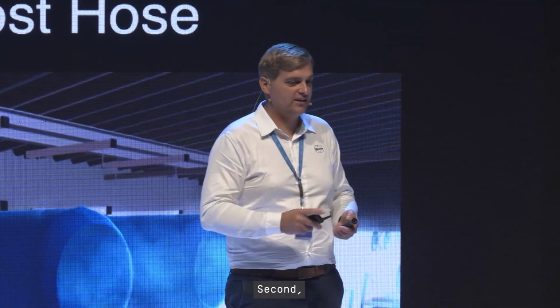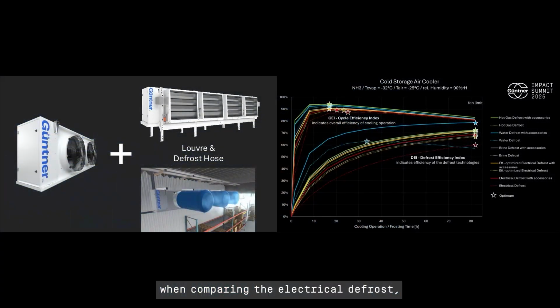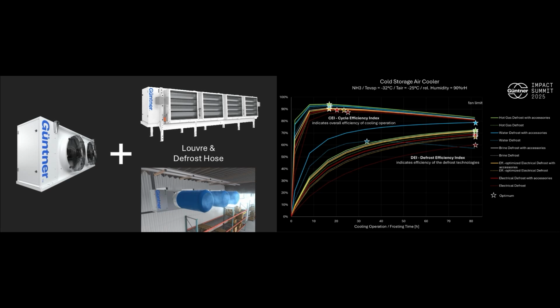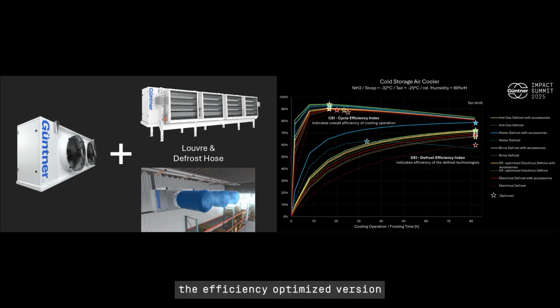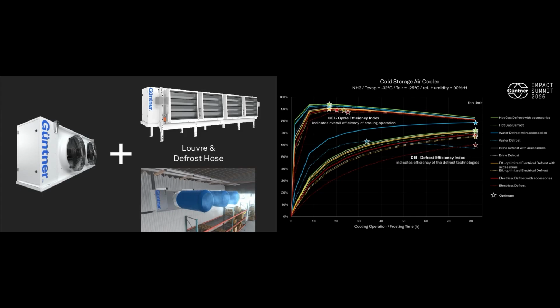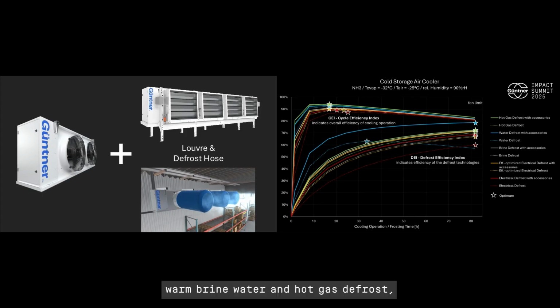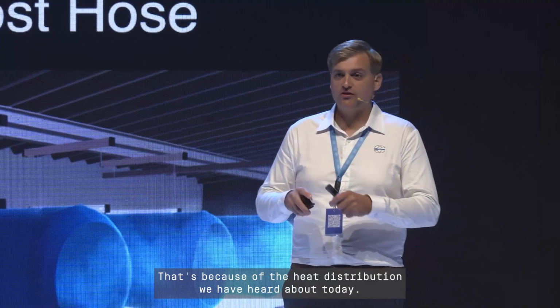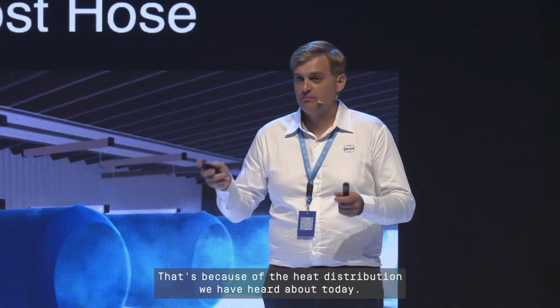Second, when comparing the electrical defrost, the efficiency optimized version is the much better one. And third, warm brine, water and hot gas defrost, they are even more efficient. That's because of the heat distribution we have heard about today.